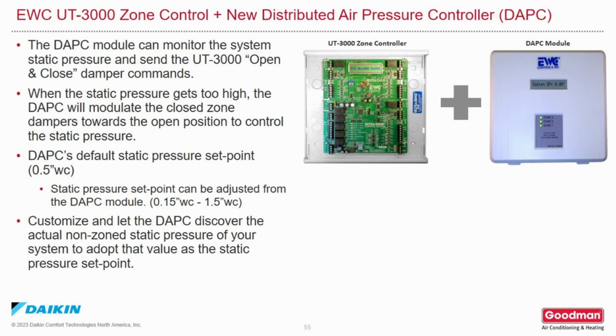When using the UT3000 zone control and adding the new Distributed Air Pressure Controller or DAPC module, the DAPC module can monitor the system static pressure and send open and close commands to the zone panel to modulate damper positions to regulate the static pressure. When the system static pressure gets too high, the DAPC will modulate the closed dampers to the open position to control the static pressure. The DAPC's default static pressure set point is 0.5 inches of water column. Static pressure set points can be adjusted, however, from the DAPC module as low as 0.15 inches to 1.5 inches. You can customize and allow the DAPC to discover the actual non-zoned static pressure of your system and adopt that value as a static pressure set point.